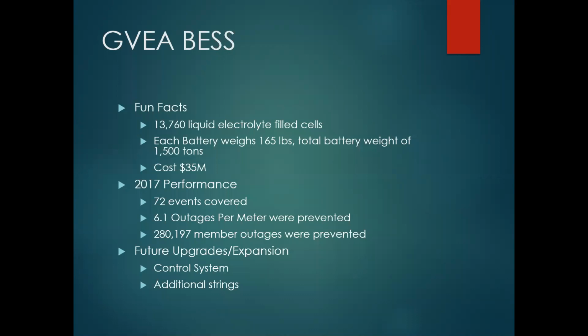So you have 72 events that were covered. How many were not covered? If there was a system event large enough to decrease the frequency to trigger the curve, it responded, so it covered all of them in that regard. However, it's really just looking at generation and transmission disturbances. So something like a distribution transformer tripping offline is not covered. There are more events on the system than that. However, it responded to and covered 100% of the events within its parameters that it should have responded to.